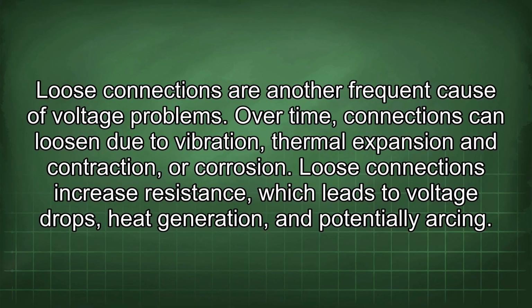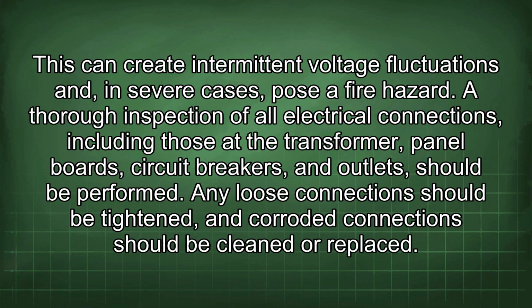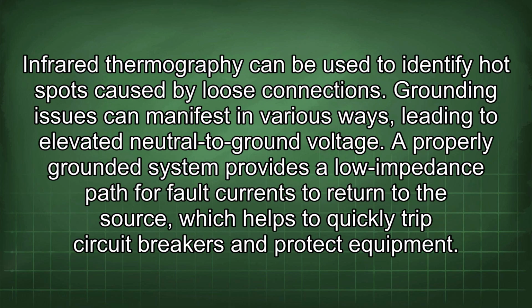Loose connections are another frequent cause of voltage problems. Over time, connections can loosen due to vibration, thermal expansion and contraction, or corrosion. Loose connections increase resistance, which leads to voltage drops, heat generation, and potentially arcing. This can create intermittent voltage fluctuations and, in severe cases, pose a fire hazard. A thorough inspection of all electrical connections, including those at the transformer, panel boards, circuit breakers, and outlets, should be performed. Any loose connections should be tightened, and corroded connections should be cleaned or replaced. Infrared thermography can be used to identify hotspots caused by loose connections.